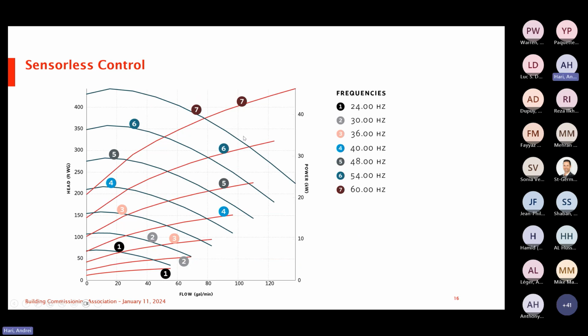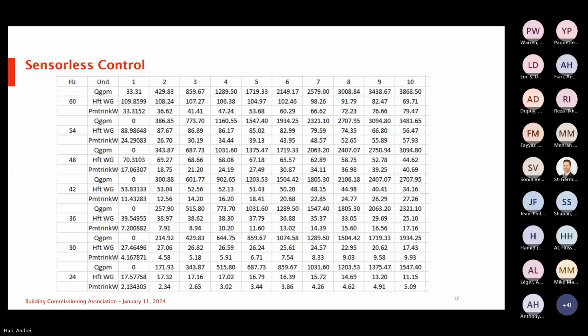The way this looks is that we're creating a matrix in the pump, and we run that in the factory. They run that pump at a series of speeds, and then they plot the data. What they're plotting is the flow to head at different speeds, and then the flow to power at different speeds. So you have this matrix of data that basically looks like this. We've run the pump at a bunch of different speeds, and at those speeds, we take the flow, the head, and the power consumed. As you can see, as the flow increases, the power changes. So now we have this matrix of data.